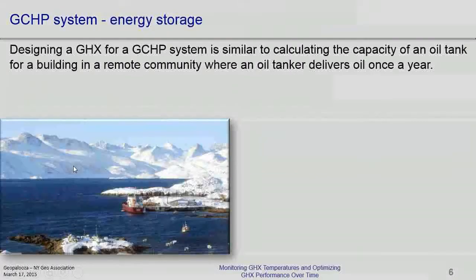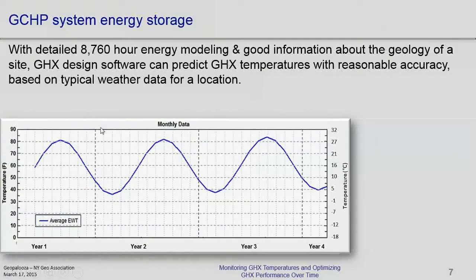So with an 8760 hourly energy model, you can get a reasonably good prediction of what the temperature should be throughout the year. And we talked about that a bit earlier. If you've got a decent energy model, you can get these kinds of numbers out of it. And if you put in hourly loads, you can get hourly predictions of what that ground loop should be doing based on a typical weather year.